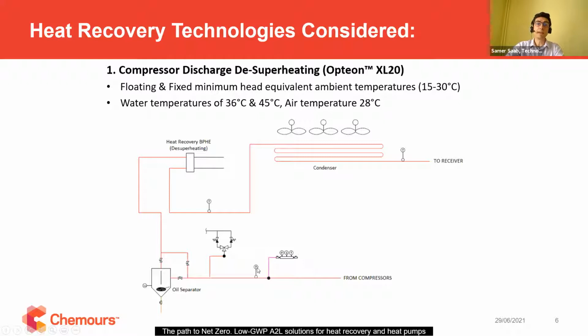We have also different parameters we can adjust into this technology. Mainly would be the condensing temperature and pressure in order to adjust the water temperature, and finally having ambient air within the supermarket blown at 28 degrees C to perform the heating.